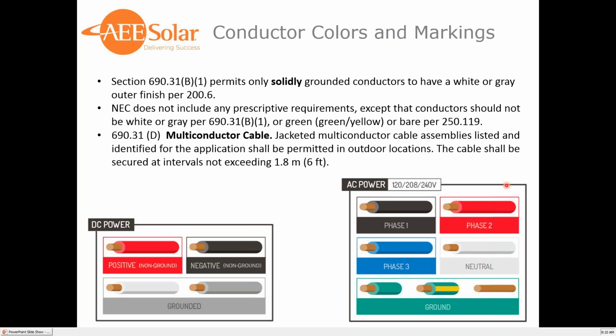Conductor color markings, colors and markings. Section 690.31(B)(1) permits only solidly grounded conductors to have white or gray outer finish per 200.6. So now that we're using inverters that are functionally grounded, nothing is solidly grounded, the code does not allow us to use white or gray on the DC side. The NEC doesn't have requirements for conductor color, except that conductors should not be white or gray per 690.3 or 200.6, or green or yellow or bare per 250.119.